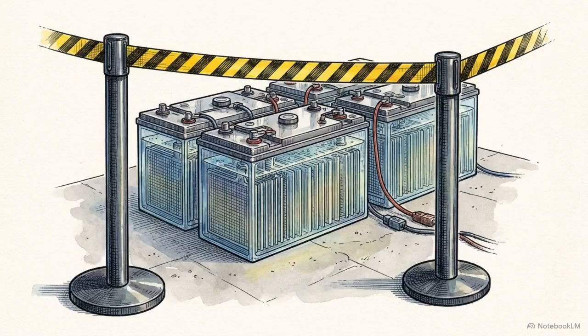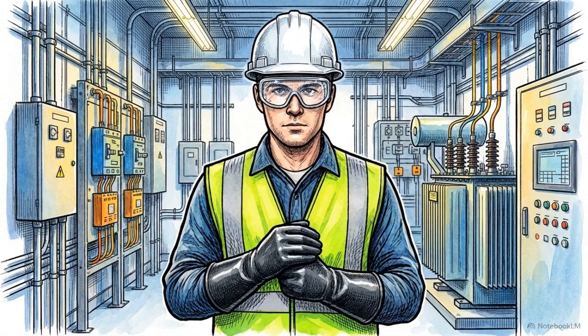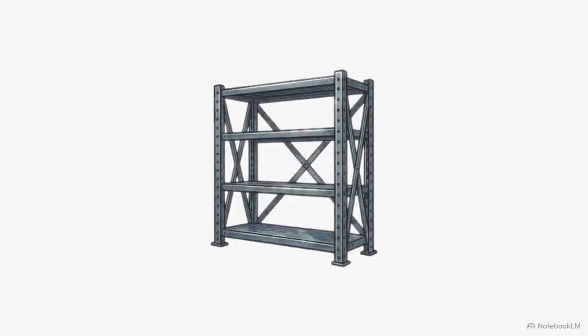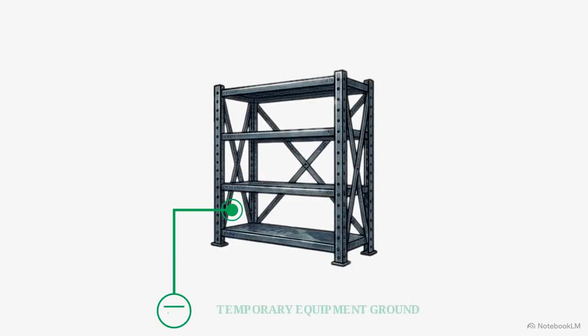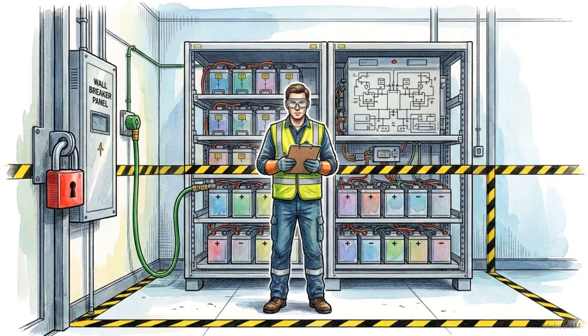Next, they establish hard, safe distance boundaries using physical barricades and warning tape. Third, the environment requires highly specialized personal protective equipment. This includes Class 0 arc flash gloves, protective eyewear, and high-visibility clothing. The final physical prerequisite is the implementation of proper temporary equipment grounding to safely redirect any stray fault currents. These absolute safety prerequisites establish the controlled environment necessary to conduct empirical testing on hazardous electrical systems.